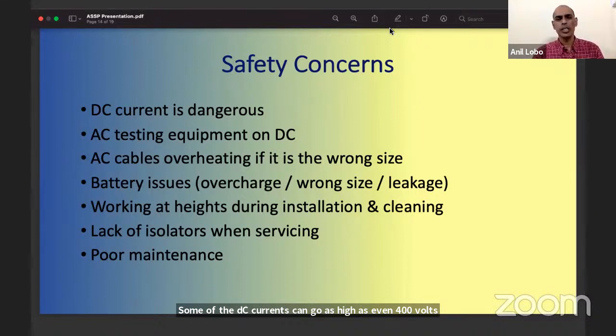On your AC side, your typical voltage will not exceed 220 volts unless you're working with a three-phase system where it can go to 415 volts. But your DC systems can go as high as 400 to 600 volts DC. So you have to be extremely careful with the DC side of the solar system.